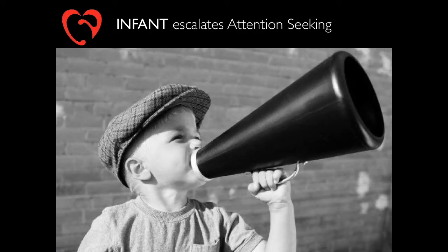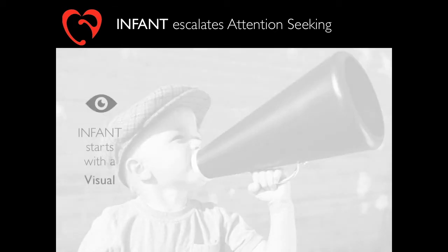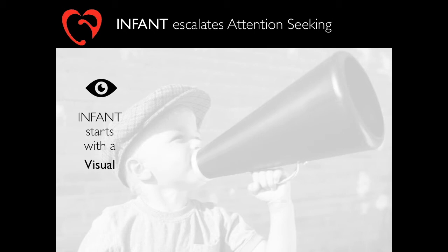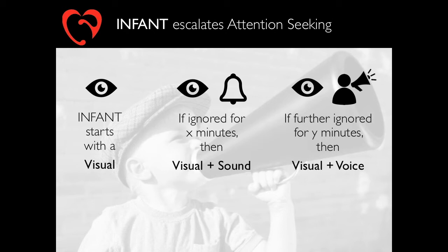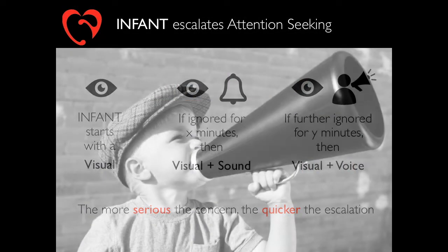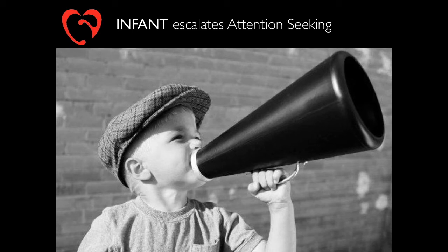When INFANT reaches a concern level of yellow or red, it will communicate its findings visually. A clinician in the room must acknowledge that they have reviewed the trace and are taking appropriate action. If INFANT is ignored for a period of time, depending on the severity of the trace, INFANT will escalate to an audible alarm tone. If a clinician still does not interact with INFANT, after a further period of time INFANT will use its recorded voice to say: 'Warning, the trace is abnormal. Senior review is urgently required.' We decided to deploy a human voice if the trace gets to serious concern and is ignored because we felt this circumstance would probably mean there was no clinician in the room. Our research shows that there is no clinician in a delivery room typically for 27% of the time, so using a human voice will empower a birth partner to summon help.